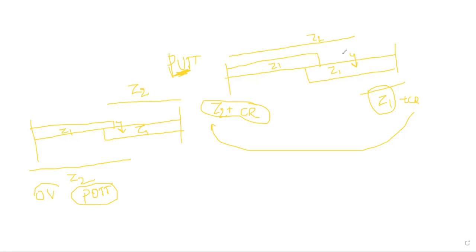Okay. Now POTT is finished. Now we will come to the PUTT. There is a fault below 80% of the line. Now A will send the carrier to B, and B will also send the carrier to A. But there is actually no meaning in this carrier, because both breakers are in the zone 1 fault. So automatically A will trip and B will trip, correct? Yes, that is the PUTT. The POTT only trips with carrier received with zone 2 pickup. Correct?